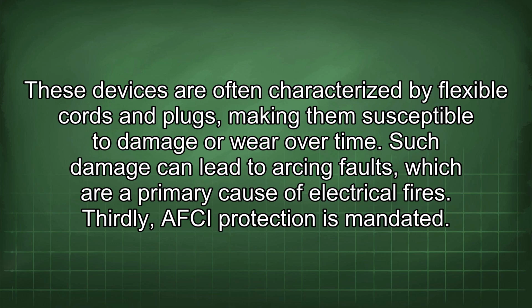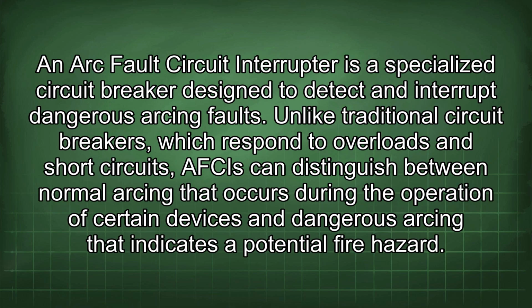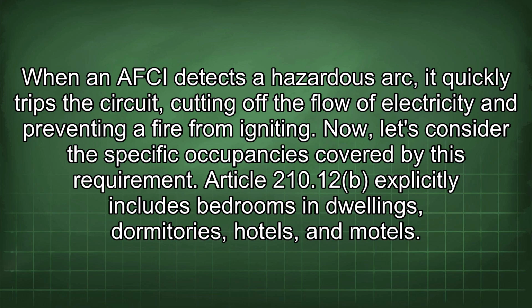Thirdly, AFCI protection is mandated. An arc fault circuit interrupter is a specialized circuit breaker designed to detect and interrupt dangerous arcing faults. Unlike traditional circuit breakers, which respond to overloads and short circuits, AFCIs can distinguish between normal arcing that occurs during the operation of certain devices and dangerous arcing that indicates a potential fire hazard. When an AFCI detects a hazardous arc, it quickly trips the circuit, cutting off the flow of electricity and preventing a fire from igniting.